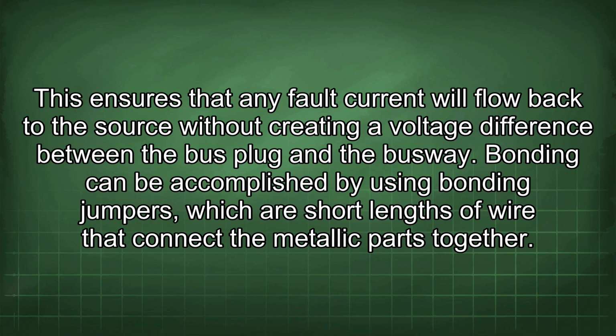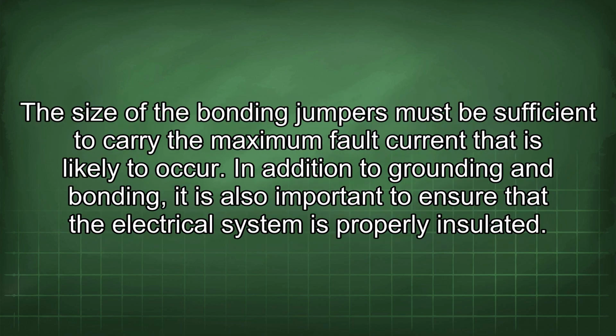This ensures that any fault current will flow back to the source without creating a voltage difference between the bus plug and the busway. Bonding can be accomplished by using bonding jumpers, which are short lengths of wire that connect the metallic parts together. The size of the bonding jumpers must be sufficient to carry the maximum fault current that is likely to occur.